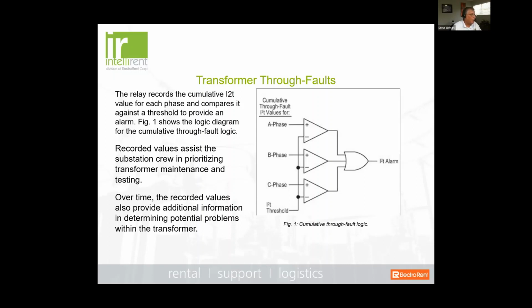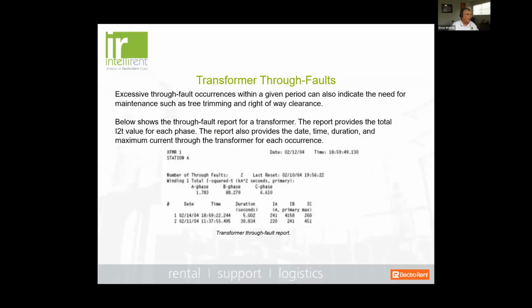But over time, let's say you have a distribution transformer in a distribution sub, and you're seeing a fairly high number of through faults. Well, that may not be to the magnitude where it would damage the transformer, but it may indicate that we've got a problem out there on that feeder, possibly requiring some tree trimming. Okay, so there is good information to get from your through fault monitor.